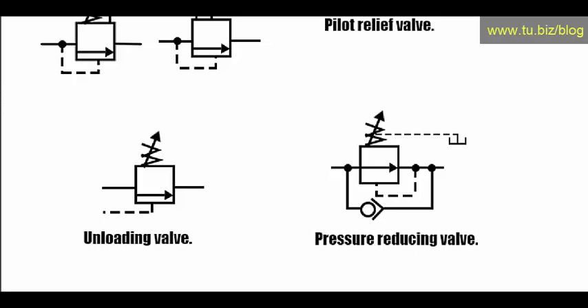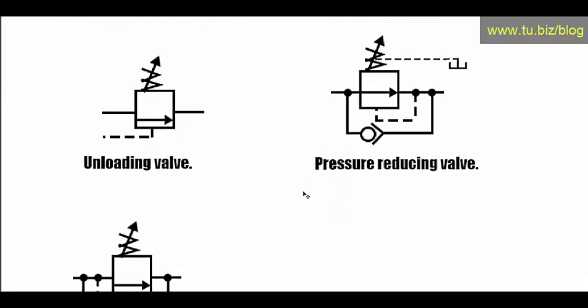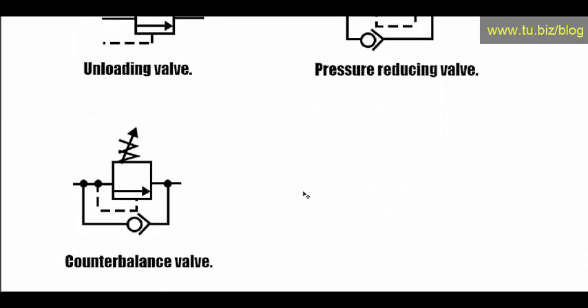Next is the counterbalance valve, which is very similar to the relief valve but it has a check valve. This allows flow in both directions — in one direction it has the pressure setting, and in the other direction the flow goes freely through the check valve.